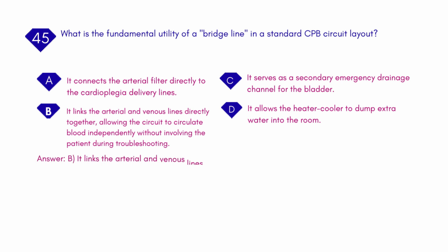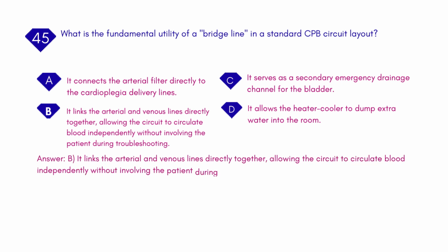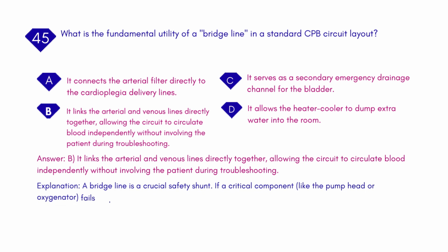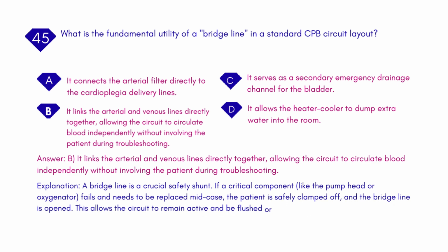Answer: B. It connects the arterial and venous lines directly together, allowing the circuit to circulate blood independently without involving the patient during troubleshooting. Explanation: a bridge line is a crucial safety shunt. If a critical component, like the pump head or oxygenator, fails and needs to be replaced mid-case, the patient is safely clamped off, and the bridge line is opened. This allows the circuit to remain active and be flushed or debugged in an isolated loop before reconnecting to the systemic circulation.